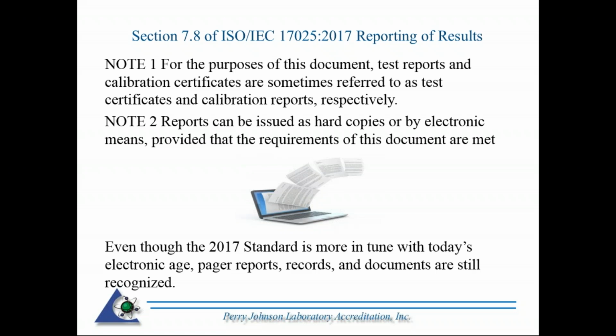And note 2, reports can be issued as hard copies or by electronic means, provided the requirements of this document are met. One thing with 2017 is that it is more in tune with the electronic age. You don't see so many references to things such as a list or indication of paper copies. However, even though the language is tailored toward the electronic age, the standard does recognize paper copies. So if your organization is still utilizing hard copies, perhaps your customers like having a hard copy delivered to them, the standard still recognizes both electronic and hard copies.